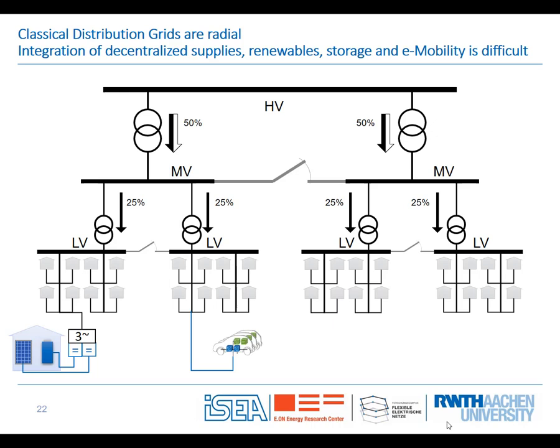In Europe, most countries use an open ring bus structure. If there's a failure on one feeder, as shown on the left, we open the circuit and then close the medium voltage breakers, so the other substation delivers 100%. That means the transformer on the right-hand side top must be able to deliver 100% of the power, which is why in normal operation they're never loaded more than 50%.